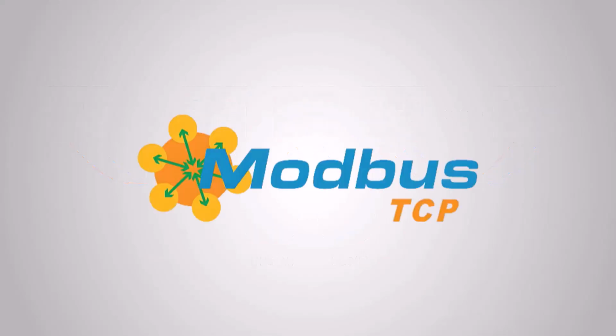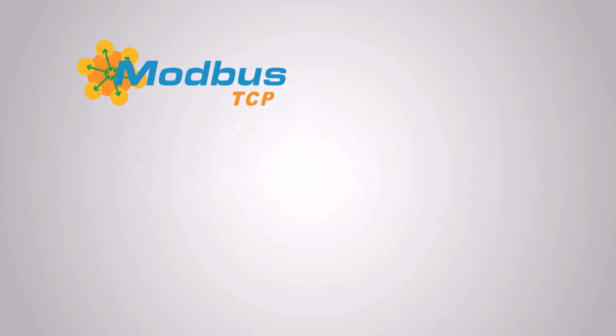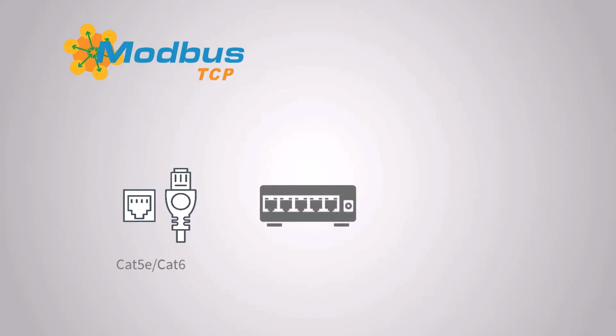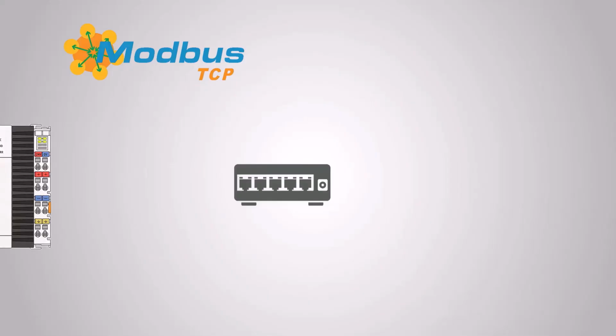For Ethernet-based communication with Modbus TCP or similar protocols, use standard Cat5e or Cat6 cables with RJ45 connectors. Connect devices through switches for multi-device networks. Assign static IP addresses in the same subnet.